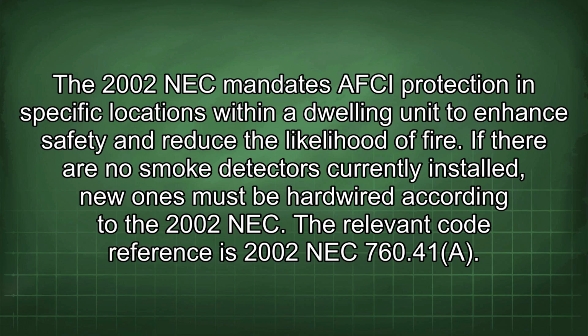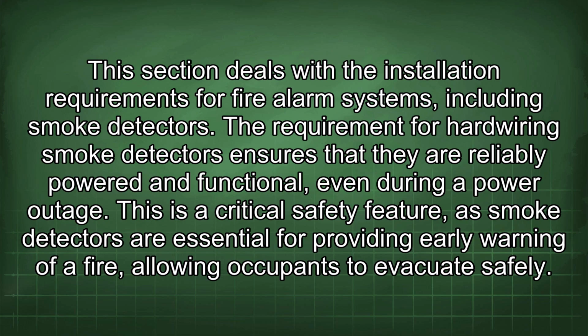fire. If there are no smoke detectors currently installed, new ones must be hardwired according to the 2002 NEC. The relevant code reference is 2002 NEC 760.41(A). This section deals with the installation requirements for fire alarm systems, including smoke detectors. The requirement for hardwiring smoke detectors ensures that they are reliably powered and functional, even during a power outage.